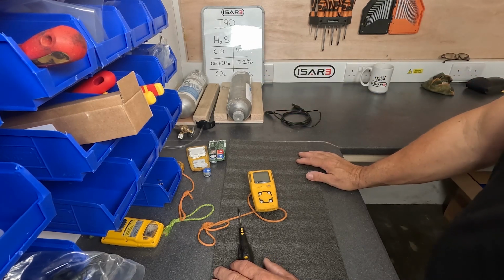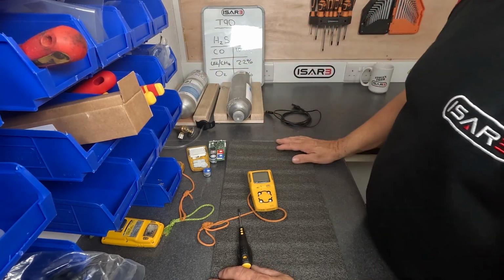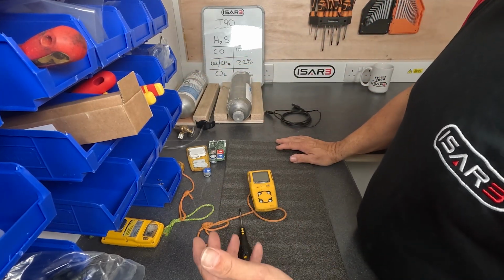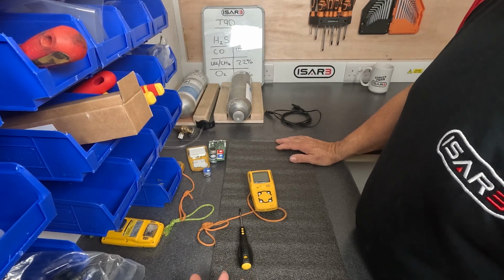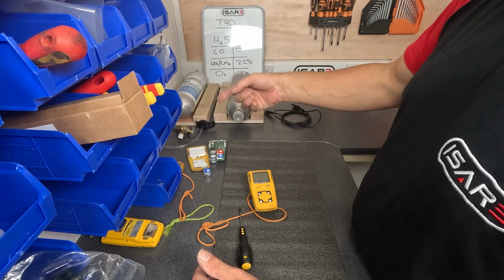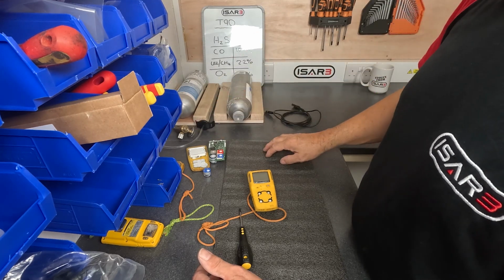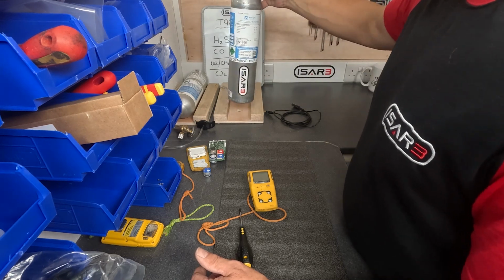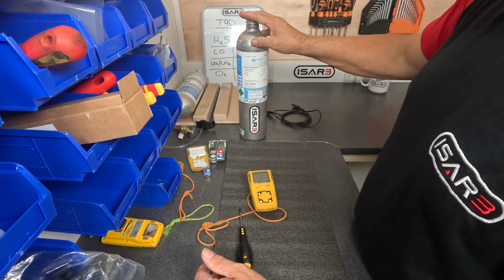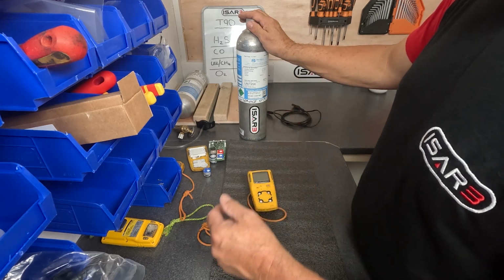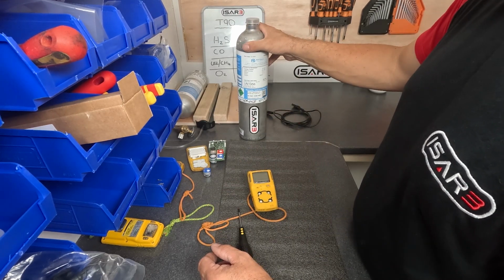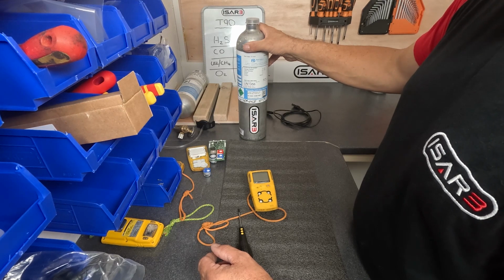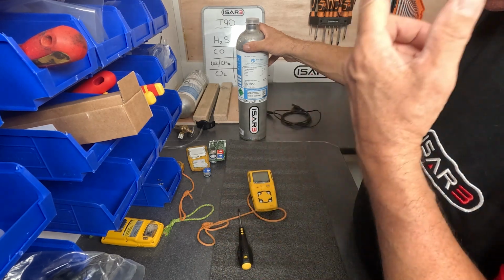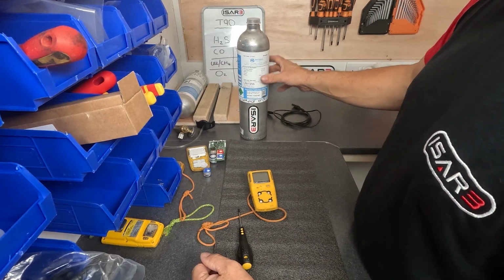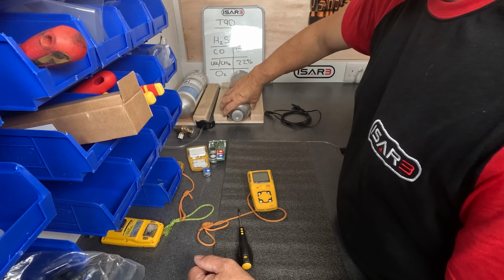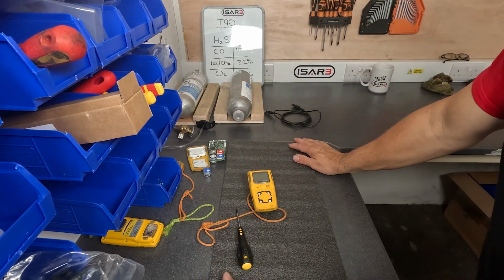The last thing I want to say is sometimes the gas on these older cylinders, as they start to wear down, particularly the H2S gas, goes off slightly because it's got some water vapor in there, especially if you've been using the cylinder on training, because students don't necessarily always open the valve when they do it. So it's good practice perhaps to have a separate cylinder, which is a new cylinder, which you don't use on training, all right, but you keep that for when you're calibrating, and then you know that the gas mix inside here, particularly the H2S, is going to be in really good condition. All right, and so when you're calibrating and resetting the curves back to what these should be, it's better done with a fresh cylinder.